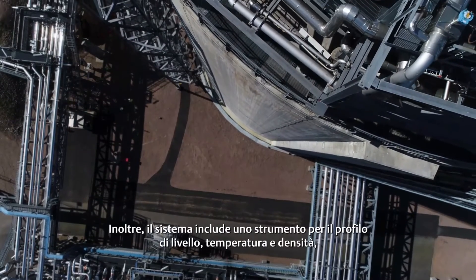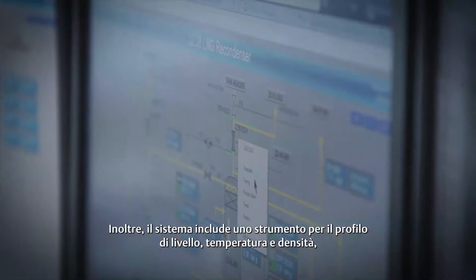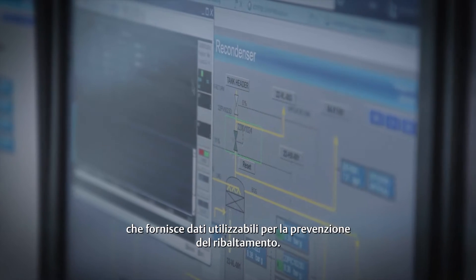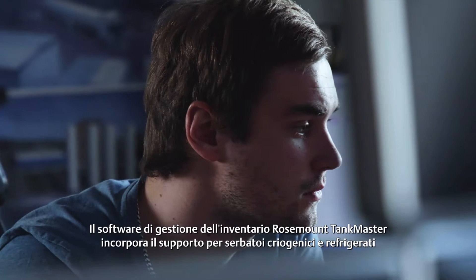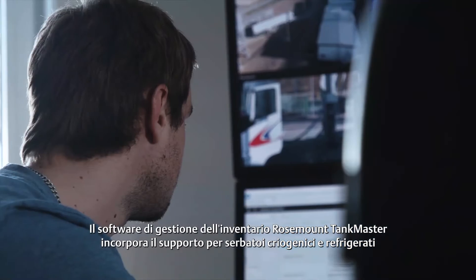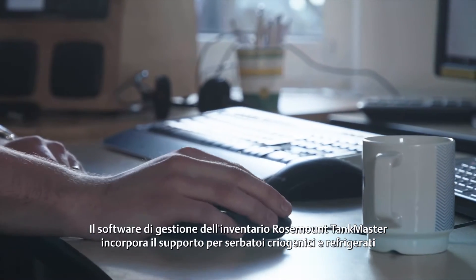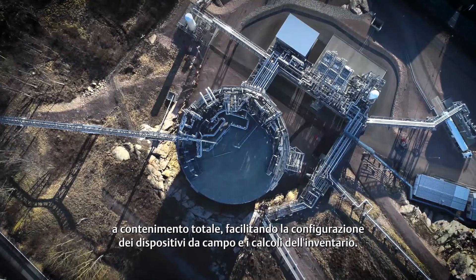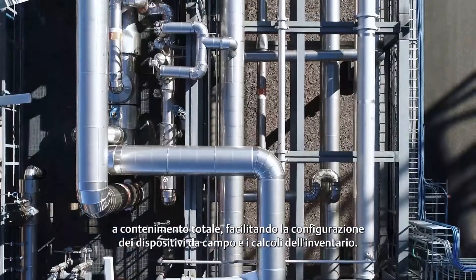In addition, the system includes a level, temperature and density profile instrument, which provides data that can be used for rollover prevention. The Rosemount TankMaster inventory management software incorporates support for full containment, cryogenic and refrigerated tanks, which facilitates straightforward configuration of field devices and enables inventory calculations.